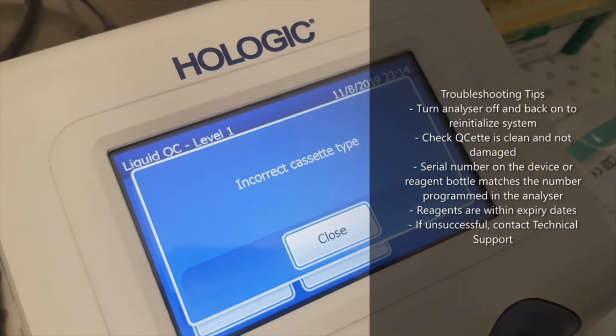General troubleshooting tips include restarting the analyzer, assessing the quality of the QCette or cassette kits, that the correct codes are programmed, and all of the reagents are within expiry dates. If problems do persist, contact the Hologic technical support.